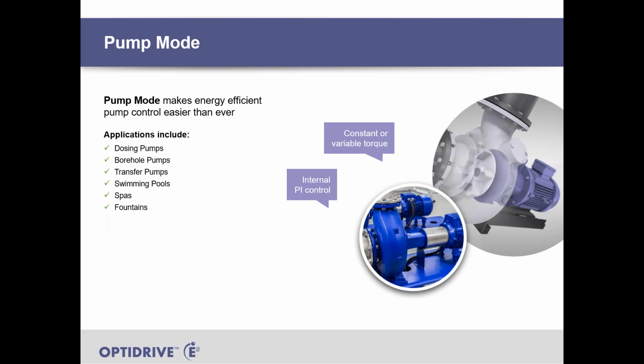We have pump mode. So we can use pump mode with constant torque or variable torque pumps. So constant torque pump would be typically like a rod pump or a positive displacement pump, whereas variable torque pump is classically a centrifugal pump. We've got an internal PI controller, so we can actually feed signal directly from a pressure transducer or a flow transducer and get the drive to automatically regulate around a desired pressure, flow, or temperature, whatever value you need.